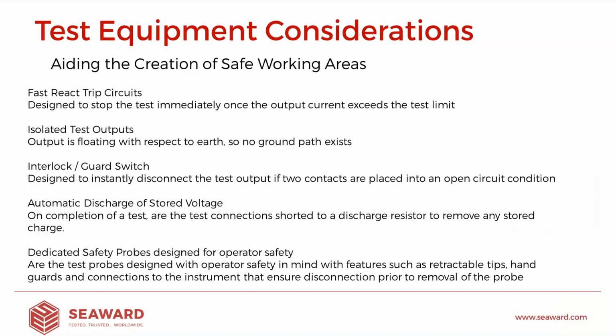So that brings me to the end of operator training. We're just going to have a quick chat about the kind of things that you can look for within your test equipment, or when you're considering purchasing new test equipment, that can aid you in the creation of a safe working area. So the first thing we're going to talk about are what we call fast react trip circuits. So a fast react trip circuit essentially stops the test the instant the fail condition's met.